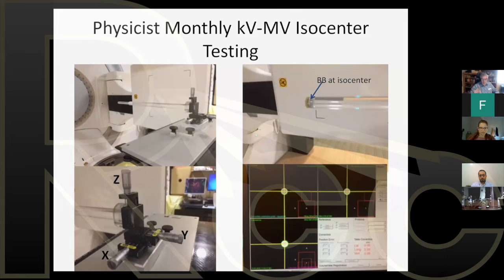The radiation beam is delivered within a millimeter to where you're imaging. In fact, this system is so sensitive on Elekta that you can adjust it to within a quarter of a millimeter. That's how accurate you can get by using these precision micrometers and this Winston-Lutz test. You can get to within a quarter millimeter accuracy of imaging isocenter and megavoltage isocenter.